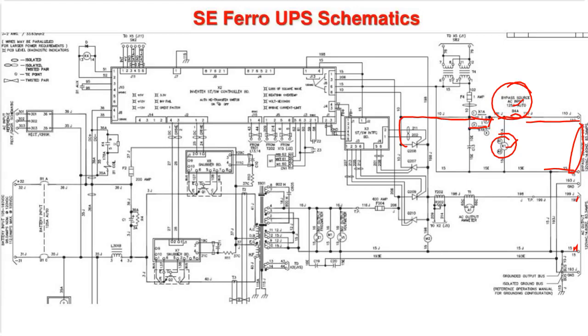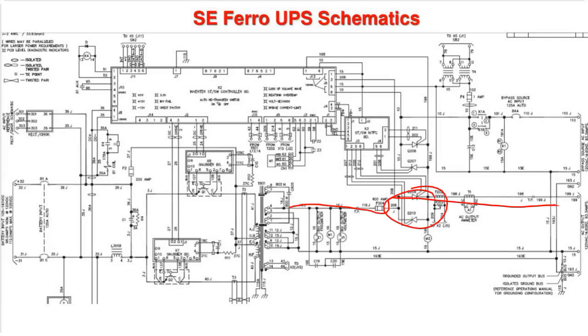This is our UL backfeed protection. Basically what it does is, remember, the inverter should be flowing through here, out through this static switch in normal operation.